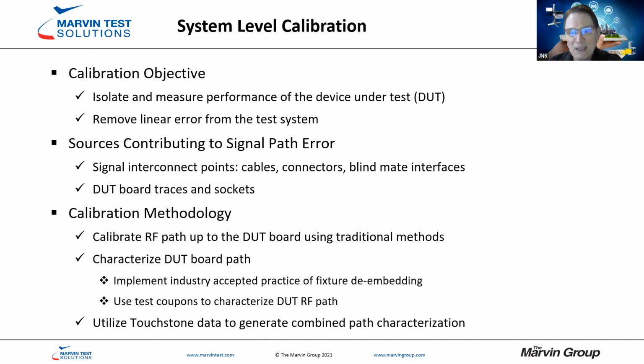Then this is all combined to provide the overall calibration solution and to accurately and, just as importantly, repeatably characterize the signal path to and from the device under test. So taking this approach, we can very accurately characterize that path, and over time we can rerun our calibrations and ensure that we're not seeing any kind of drift.